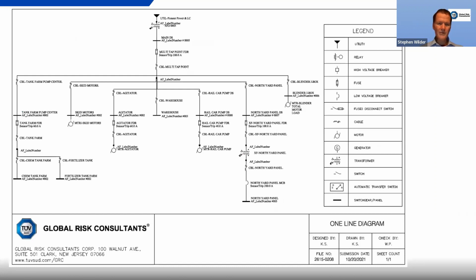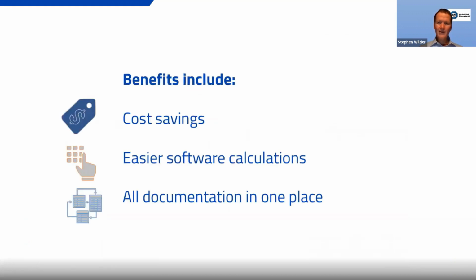Well, the short circuit, coordination, and arc flash, they're all really needed, and the greatest benefit is cost. There's a large cost associated with surveying the site, creating the model, writing each report. It obviously saves you a lot of time if you do all these things once and just add sections for them, rather than make 3 visits, 3 models, 3 reports. It's also better to maintain it if you have one calc in one place, rather than have 3 different calculations that you have to maintain. We use the same software. Every company uses the same software for all 3 calculations. So there's only one model that's created. It's just different scenarios are running.